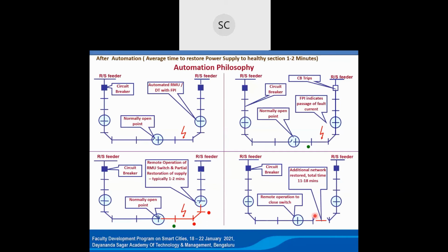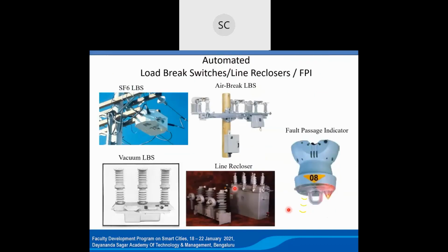So what happens? Let us assume I am providing a timeout of 1 minute. When the tripping happens, the auto recloser will wait for 1 minute before reconnecting to the load. So after the timeout of 1 minute, it will reconnect again to the load. If it is a temporary fault, like a tree falling due to wind and other things, automatically it has been set right. So there will not be interruptions. The auto recloser will continue.